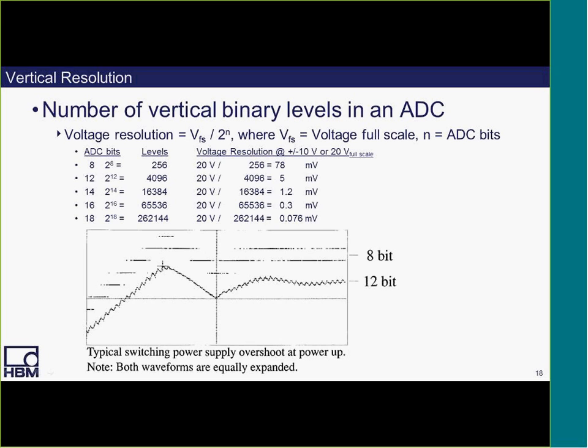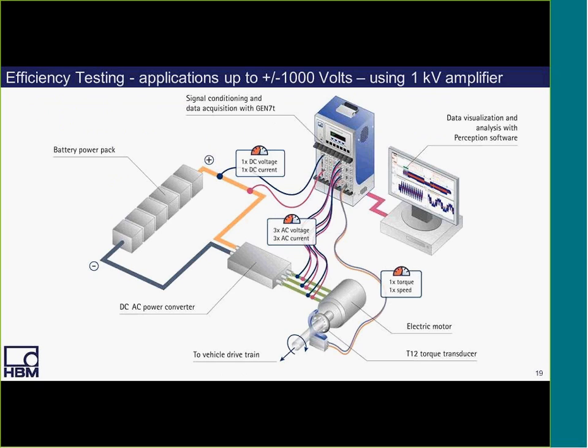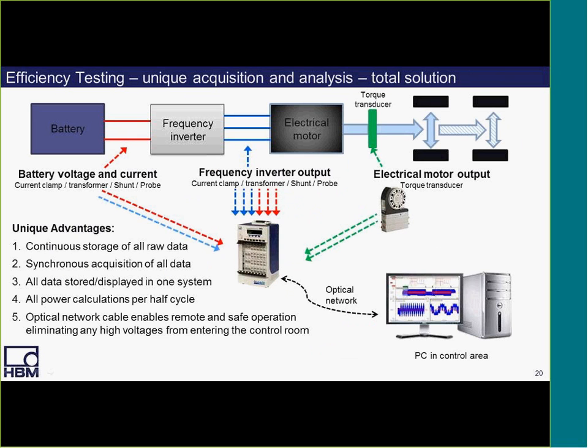Now the chart just above the diagram gives a quick representation of the smallest resolvable voltage based on the vertical resolution of each digitizer over a 20-volt full-scale range as one example. Here in this diagram, I'm showing the high voltage and high current direct connections going to the 1kV amplifier, plus the torque and speed connections all going to one single system.